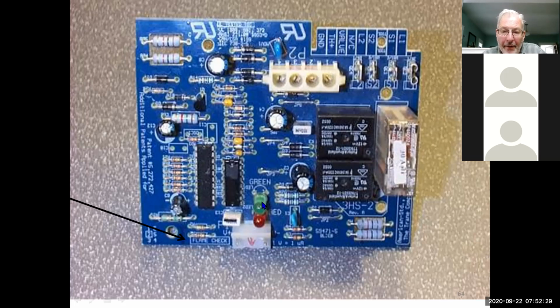We also have on the board a LED, a red one and a green one. The green one is just your heartbeat to tell you if the system's in heat or standby. We have a couple of diagnostics. We have a 2-flash, which is a flame failure. We have a 4-flash, which is a limit, or a 5-flash, which is a gas valve circuit issue. We don't have a 3-flash on here because there's no pressure switch.